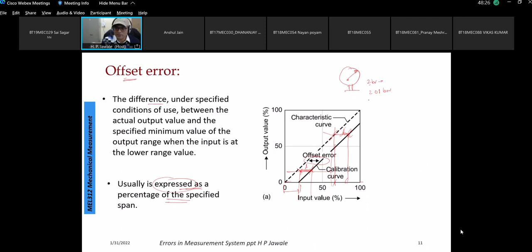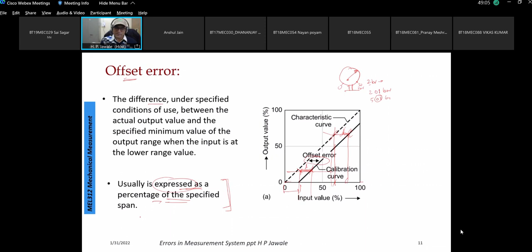Suppose the full range is from 0 to say 20 bar. Then I have to specify that the maximum offset error in this equipment can be some percentage of the specified span, say 0 to 20 bar. This is how we specify. You first of all calculate or estimate the error and then specify how much it can be on the given span of the measurement. I think this will again come across in the next slides: how to specify it and what is the meaning of the span.